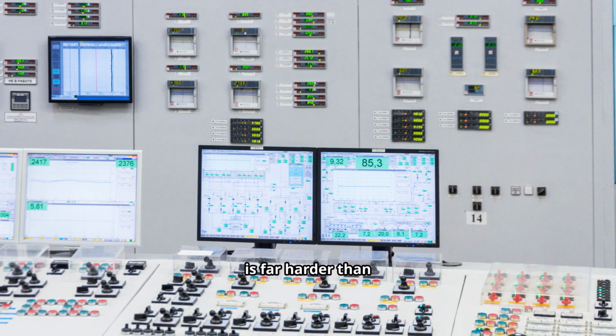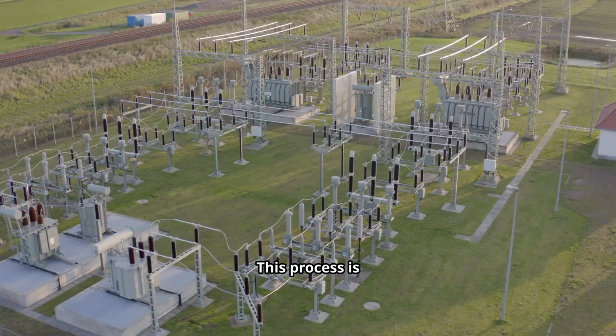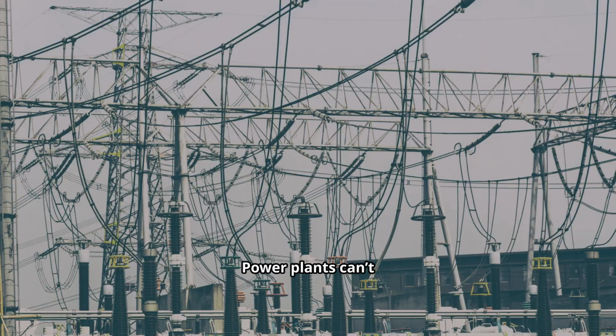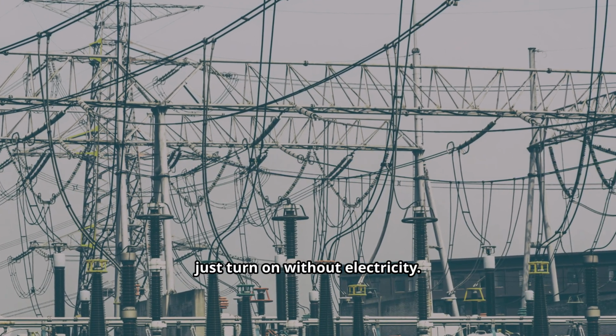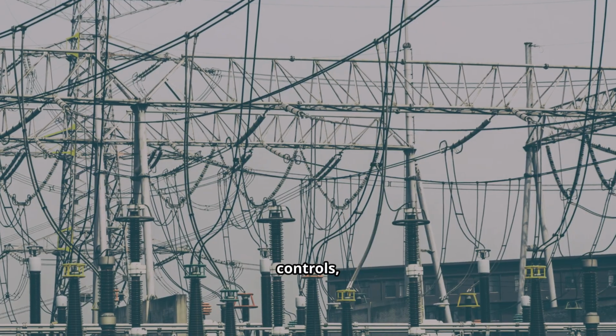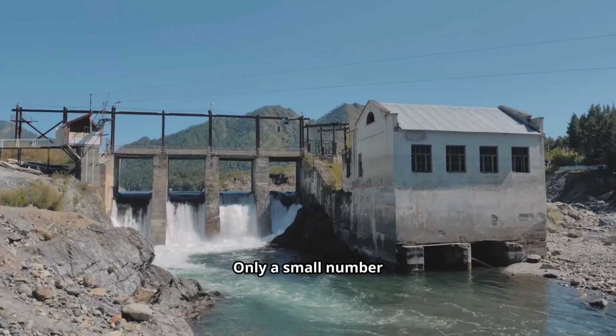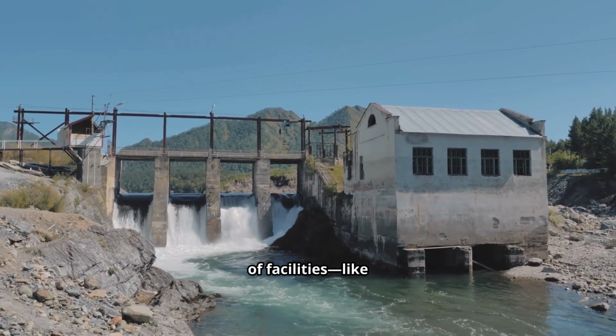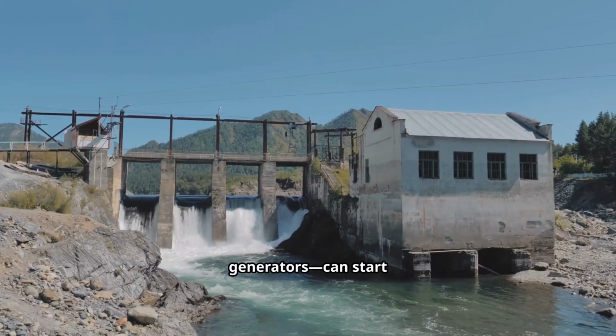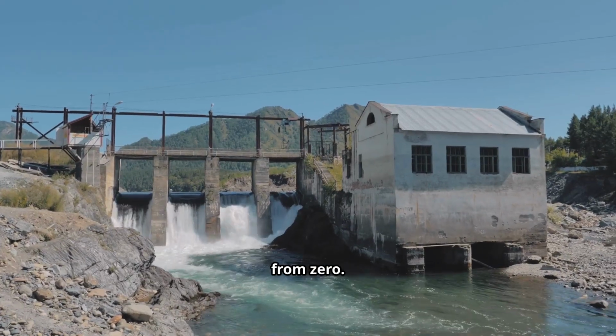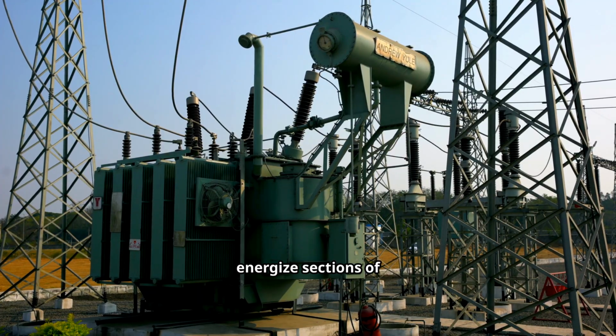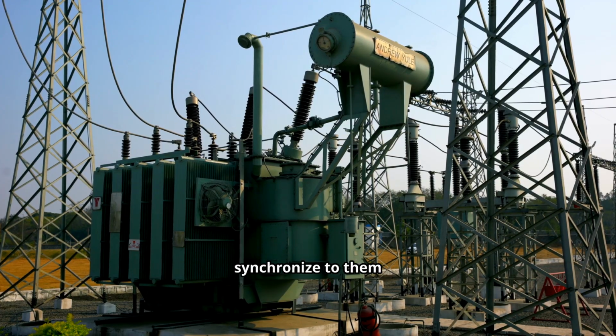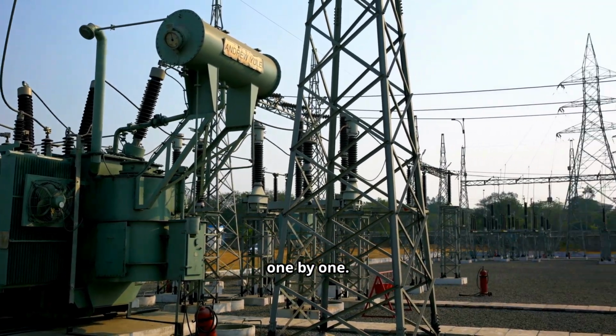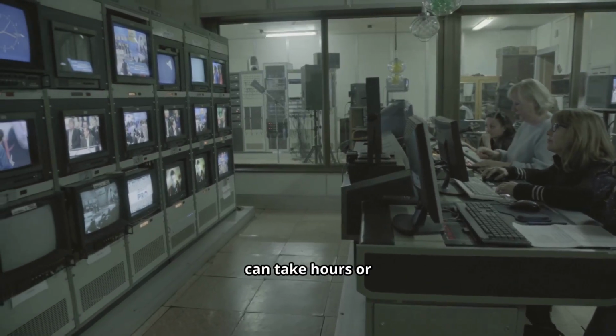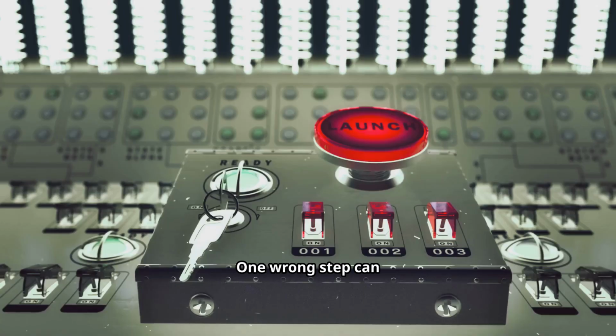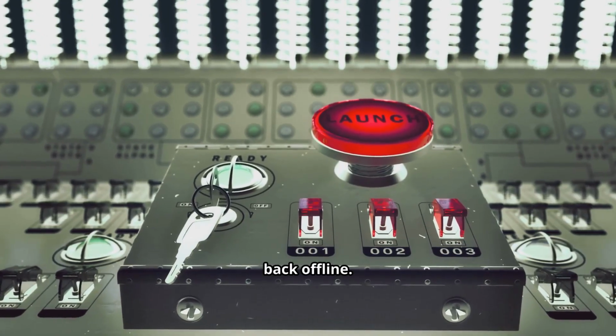Restarting the grid is far harder than shutting it down. This process is called black start. Power plants can't just turn on without electricity. They need power for pumps, controls, and cooling systems. Only a small number of facilities, like hydro plants or special generators, can start from zero. These plants slowly energize sections of the grid. Other generators synchronize to them one by one. It's a careful, manual process that can take hours or even days. One wrong step can force everything back offline.